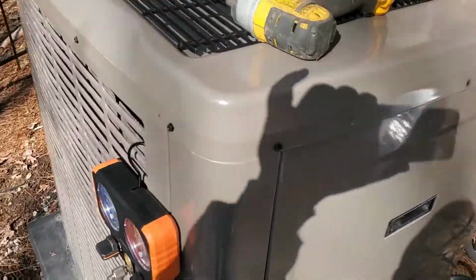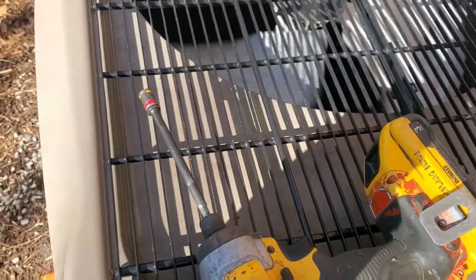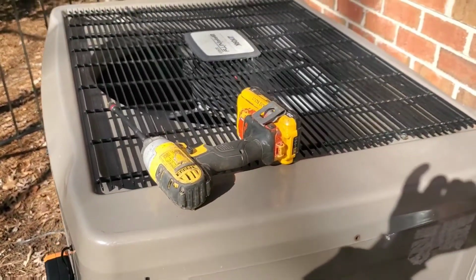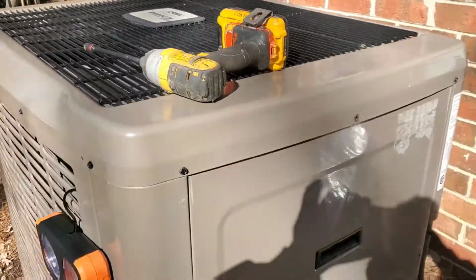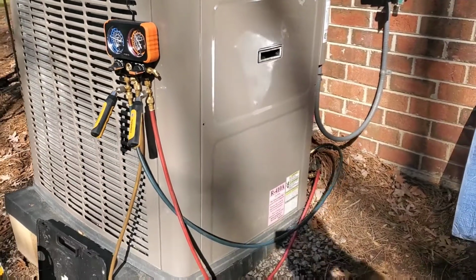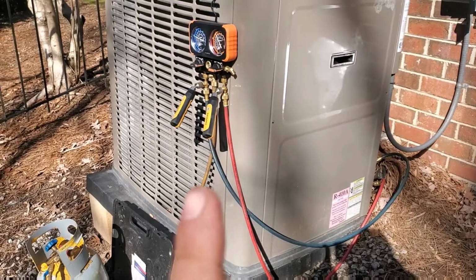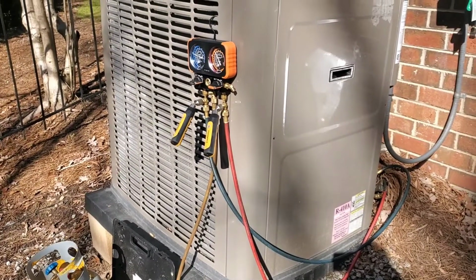A lot of these units, you can just take a few screws off and you can get the compressor or the condenser fan out of the way and take your readings. So do that when you're messing with the charge, when you're diagnosing complicated problems. It's well worth the time to do it. But in the end, don't forget to get your probe back.